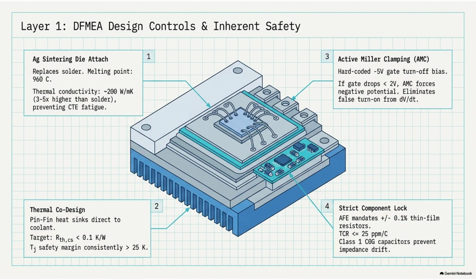But I have to push back on the physical reality of this setup. If this NTC sensor is physically glued to the copper board, sitting next to the power chip, isn't there an unavoidable delay? Heat doesn't teleport. If that switch chip suddenly experiences a 390 amp short circuit and spikes in temperature, that heat wave has to physically travel through the atomic lattice of the silicon, down through the sintered silver glue, across the copper traces, and then finally into the NTC sensor. It has to conduct through the physical mass of the materials. So isn't there a severe thermal lag between the chip actually overheating and the sensor finally feeling it?